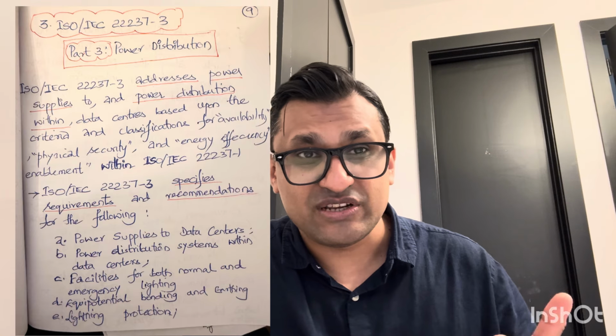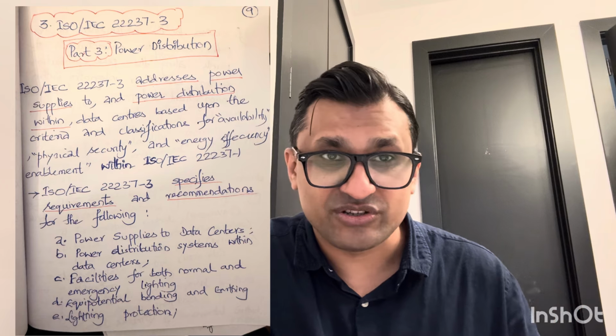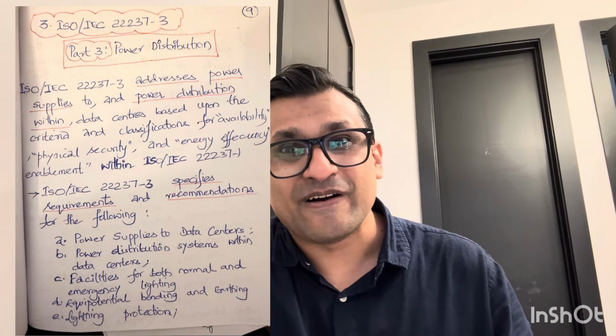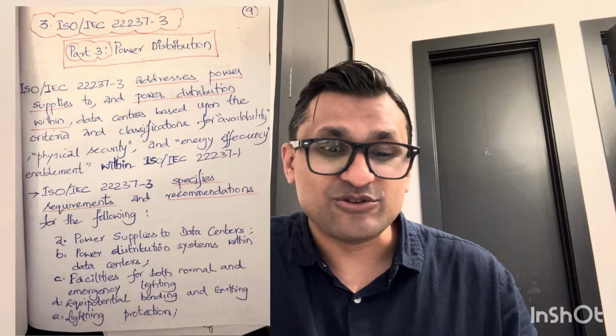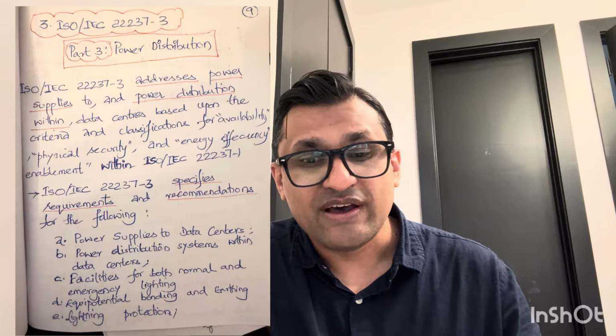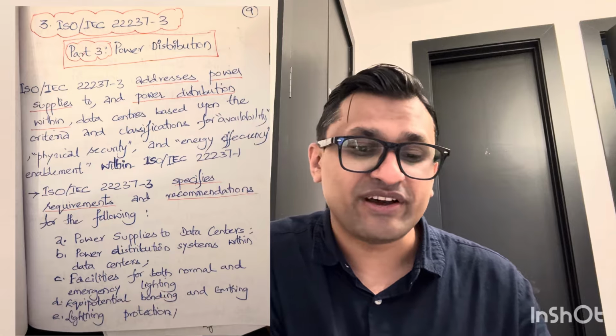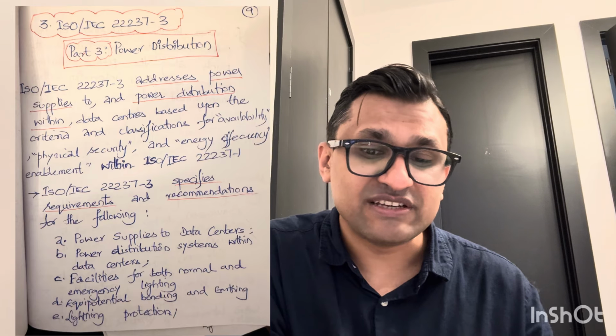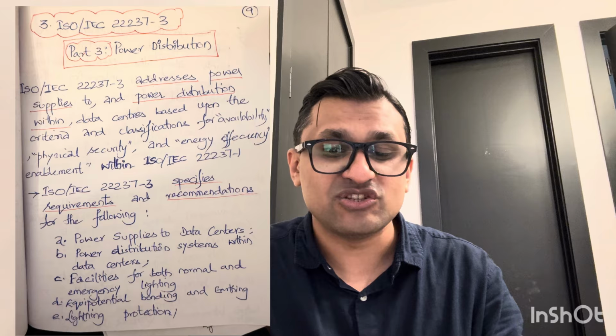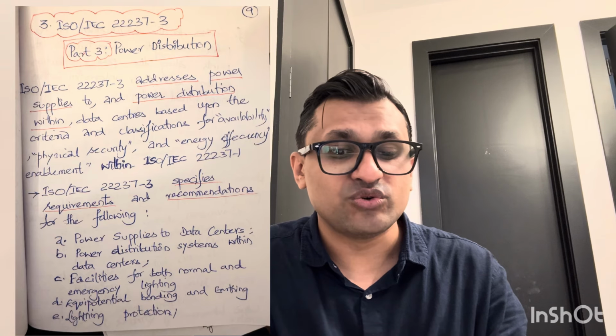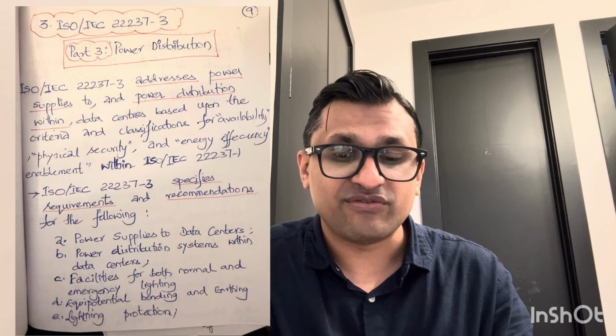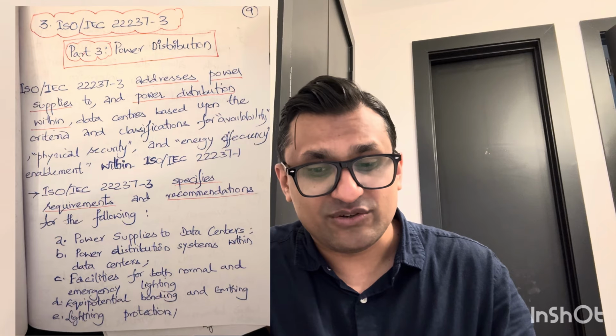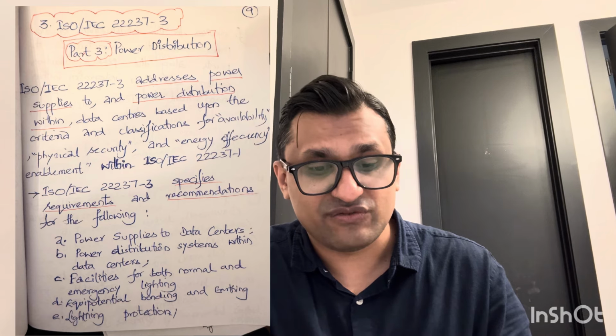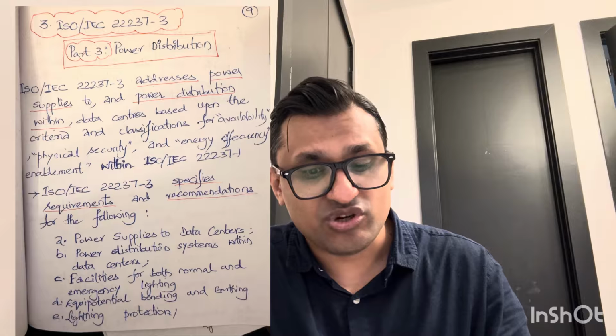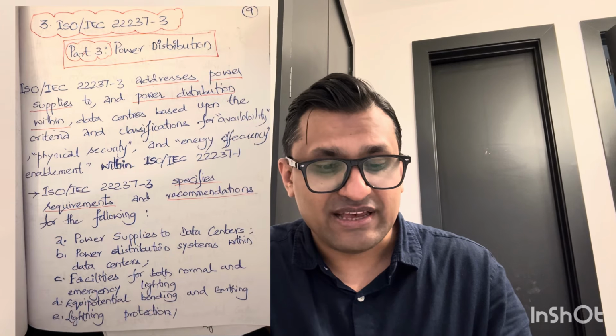ISO/IEC 22237-3, Part 3, is power distribution. You have the building, now you need the power so the building can run. It addresses power supplies to and power distribution within data centers based on the criteria and classifications for availability, physical security, and energy efficiency enablement within ISO/IEC 22237-1. It specifies requirements and recommendations for power supplies to data centers, power distribution systems within data centers, and facilities for both normal and emergency lighting.